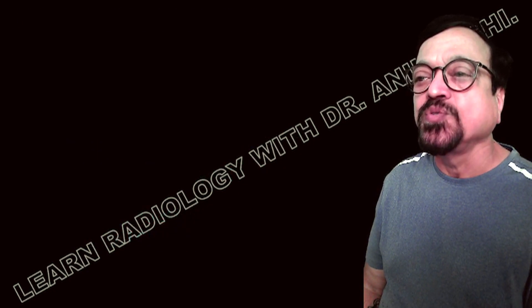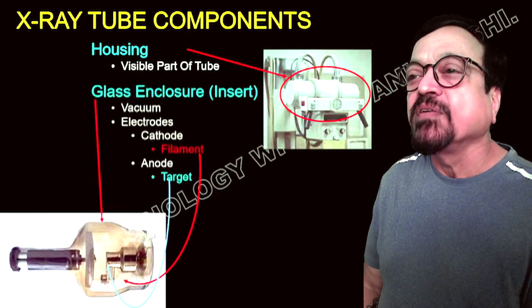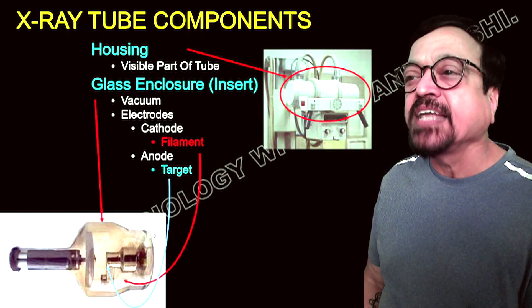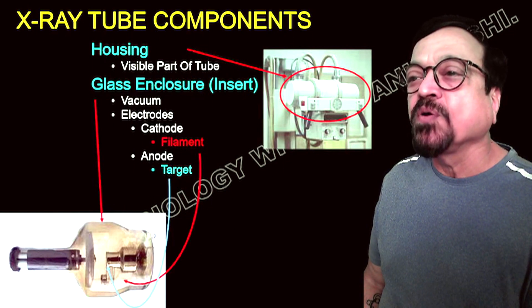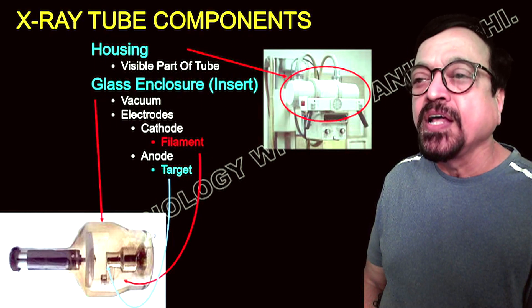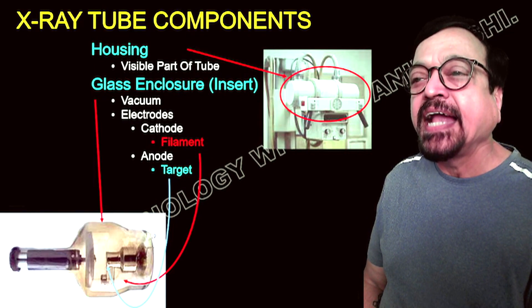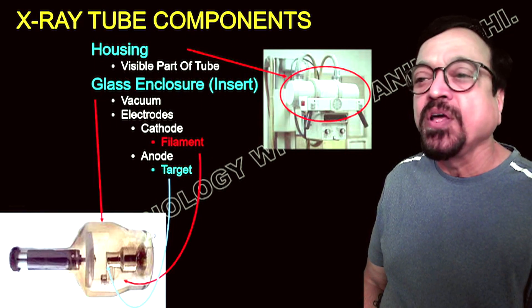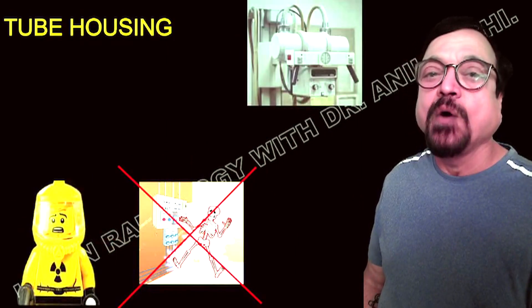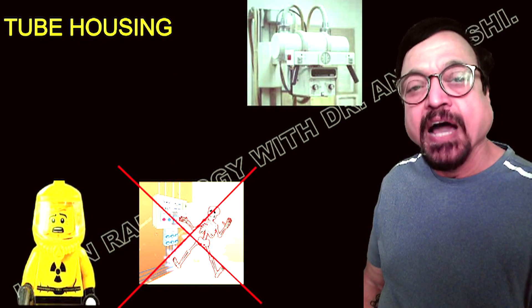The components of the x-ray tube include: the housing, which is what we see from outside; the glass envelope — also called the insert — which is a vacuum; and the electrodes, which include the cathode (the filament) and the anode (called the target).